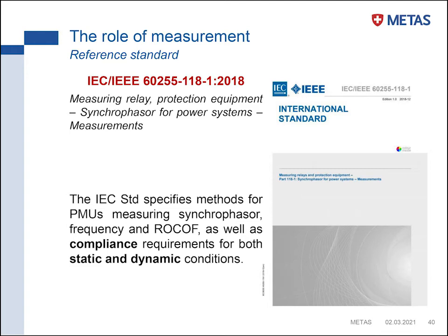So the idea is that the PMU will not be just an instrument for taking measurements, but will take also a control action and will decide whether a line has to be opened or not, whether a line is congested or not. So we are talking about not only an observer, but also an actuator. The IEC standard specifies some methods for measuring the synchrophasor, the frequency, and ROCOF, but also some compliance requirements, as any other standard.